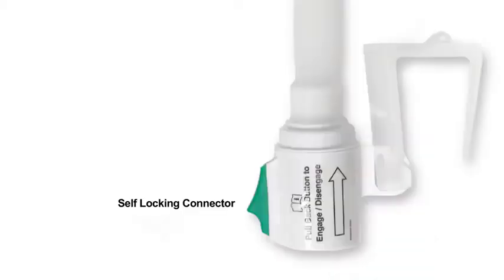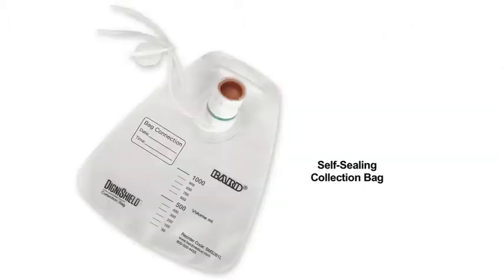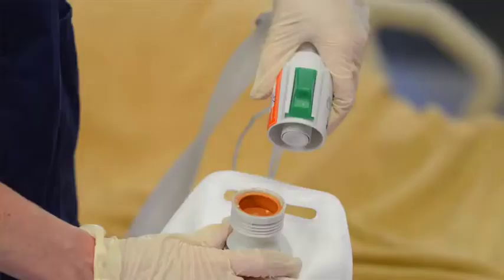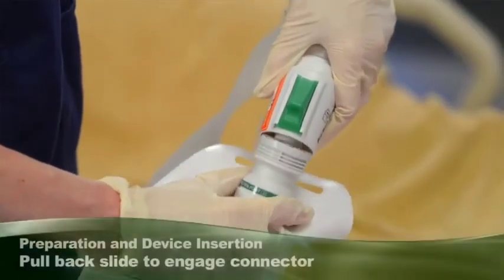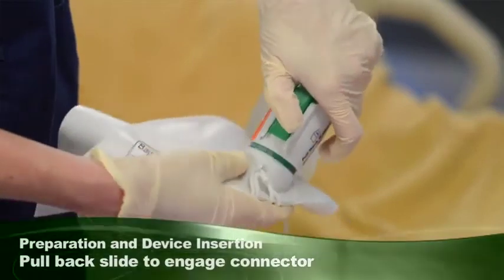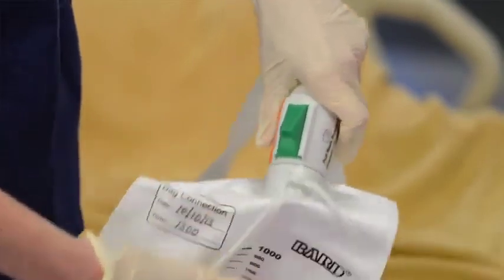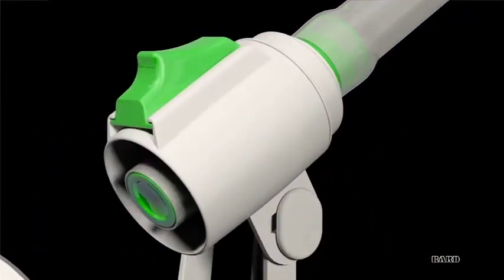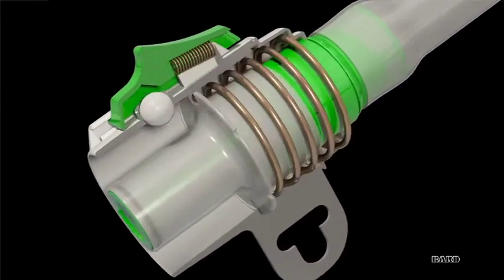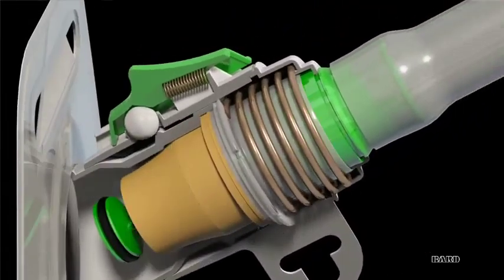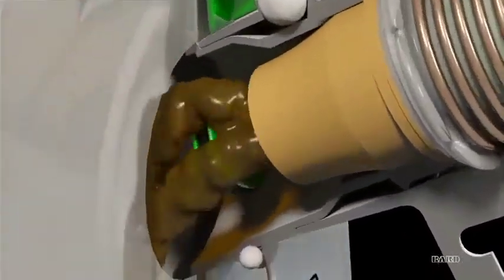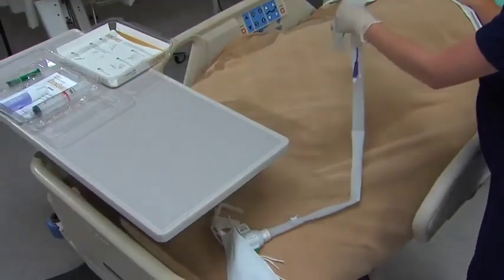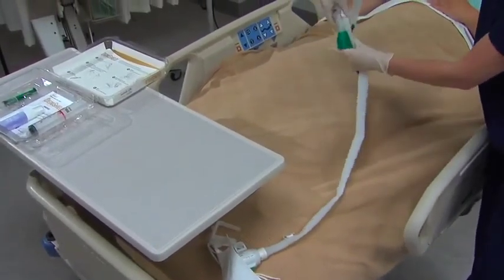A sample port provides closed system access for fecal sample collection. And a self-locking connector at the distal end of the catheter is designed to help maintain a closed system along with a self-sealing collection bag. To set up the system, attach the collection bag to the catheter by inserting the socket connector into the collection bag hub. Note that the self-locking valve connector and self-sealing bag hub are designed to maintain a closed system and minimize contact with stool when the bag is replaced. The catheter should be completely unfolded and the collection bag should be extended toward the end of the bed.